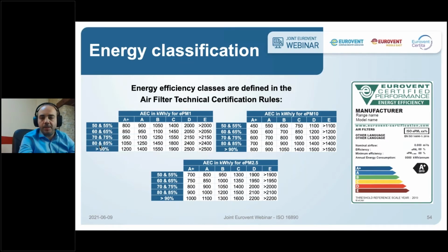As PK explained earlier, you can see that, for example, for ePM1, the best class is for air filters consuming less than 800 kilowatt hours per annum, whereas the lowest class corresponds to more than 2,000 kilowatt hours per annum. So it's more than double the difference between a very efficient filter and a not efficient filter. So this may have a big impact overall in the system if you take it into account. And what is very important to see on those tables is that the energy classes and the rules to define the energy classes are always based first on the filter efficiency class.